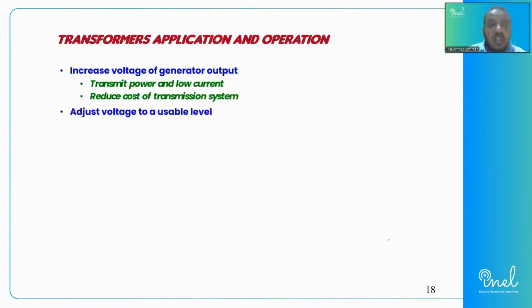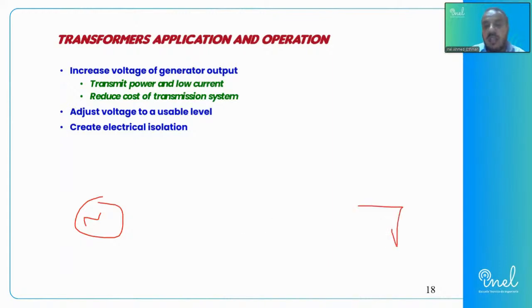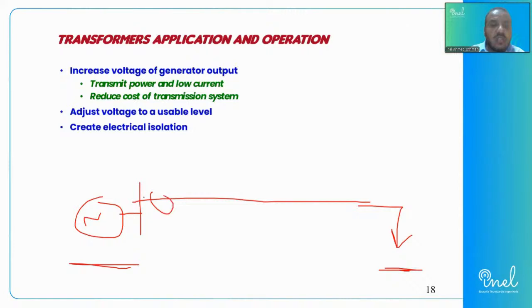So the transformer is used for transmitting power. We apply the transformer to reduce transmission losses. If we have a power grid, such a grid has a source and has a load at the end. We have a generation center and we have a load center. To be able to transmit the power over a long distance, we should use a transformer to step up the voltage, reducing the current, transmit the power, and at the end, we can step the voltage level back to be suitable for the load.